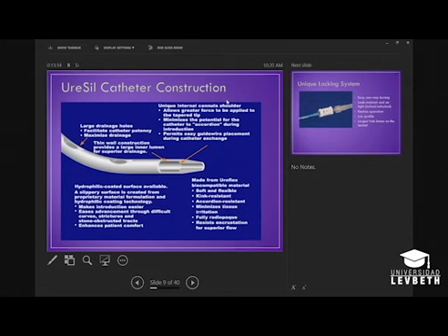This is a blown up version of the catheter tip. At the top left, you'll see the large drainage holes, and you can see what I was referencing, the skived cut. The middle of that is punched and the sides are skived, so it's a skived cut hole. Cook would be just a punched hole. We have a unique tip taper that allows for smooth insertion, so you don't have that accordion. And all of our catheters, again, are hydrophilic coated. This allows for patient comfort, it tracks well, slides in easy. They're made from a biocompatible material, polyurethane. It's soft and flexible, kink resistant, minimizes tissue irritation, and it's fully radiopaque, meaning they can visually see it.